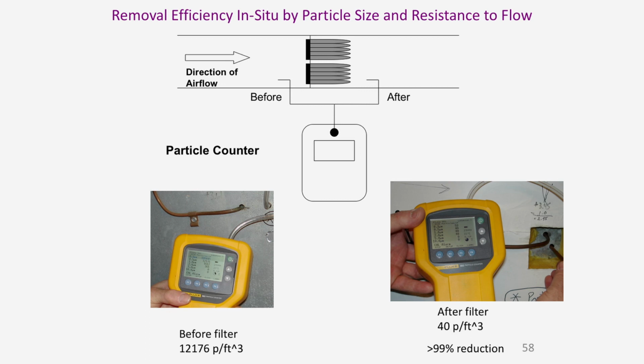You have to be careful. You have to develop a technique. You don't want to suck the dust from the insulation and in that air balance hole into the particle counter, because it will ruin the optics. But yet, you can see before and after the filter that we have very efficient filtration from this Pennsylvania hospital that I tested a few years ago.